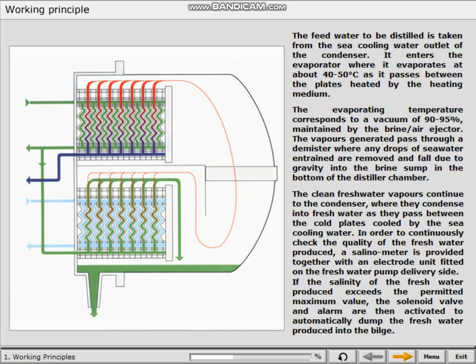The clean freshwater vapours continue to the condenser, where they condense into fresh water as they pass between the cold plates cooled by the sea cooling water. In order to continuously check the quality of the fresh water produced, a salinometer is provided, together with an electrode unit fitted on the freshwater pump delivery side. If the salinity of the fresh water produced exceeds the permitted maximum value, the solenoid valve and alarm are then activated to automatically dump the fresh water produced into the bilge.